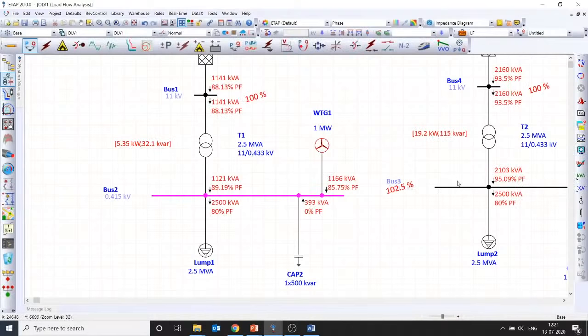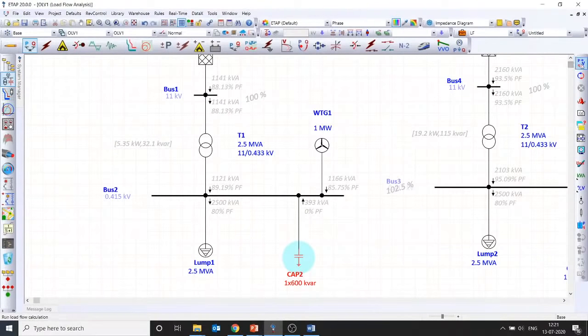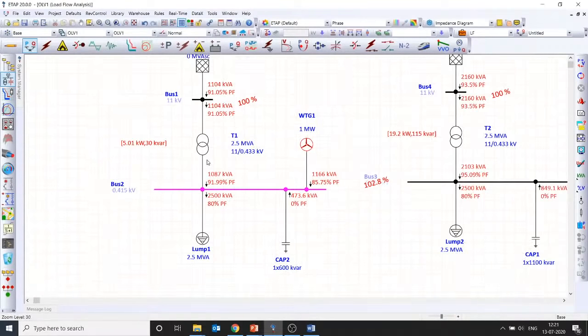Maybe 500 may not be sufficient, but at least maybe 600 will do instead of 1100. So if you have a doubly fed induction generator which has the capability to generate reactive power, that's better, it will be able to maintain the power factor. Here you can see, without the wind turbine generator, you may need about 1000 kVAr to maintain the power factor. But with a doubly fed induction generator, the capacitor bank rating needed is less. Simple reason: this wind turbine generator is able to generate reactive power.